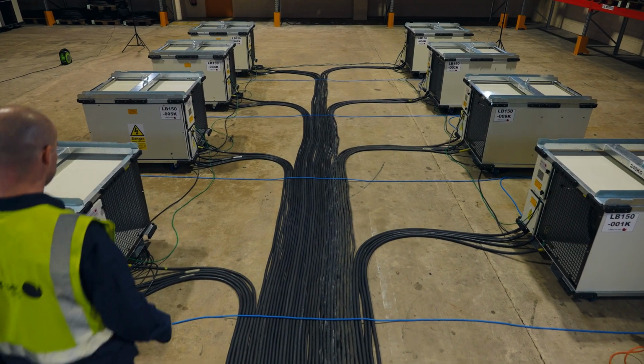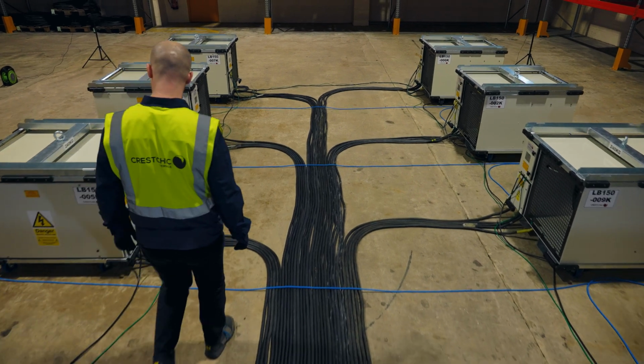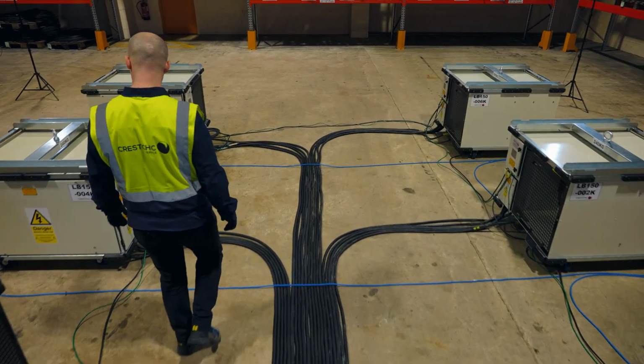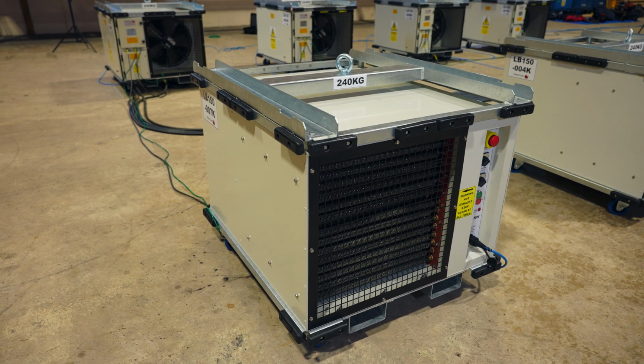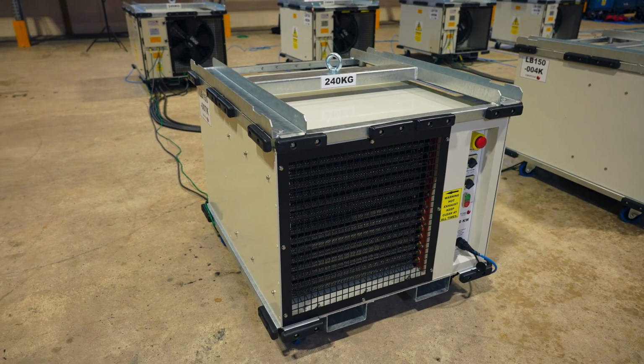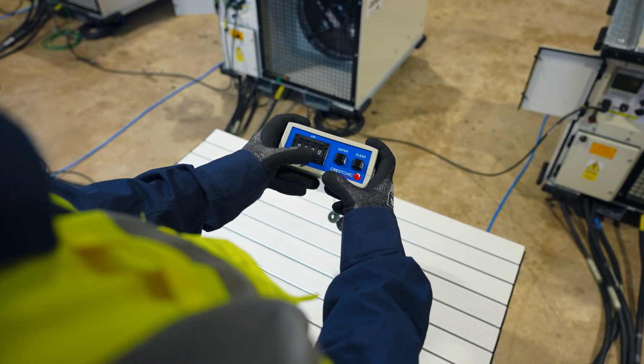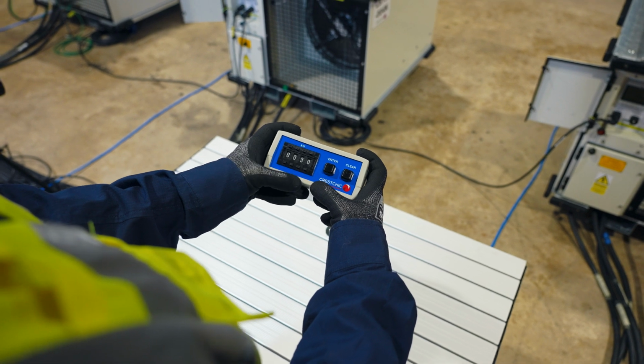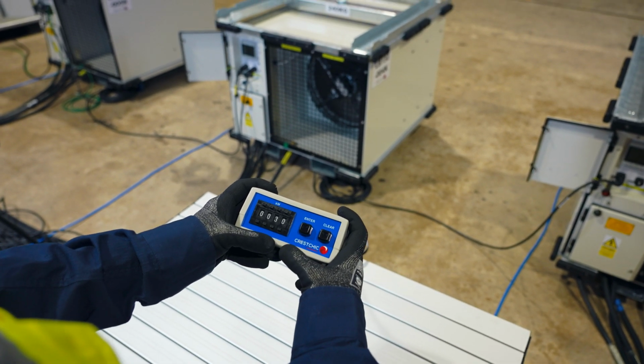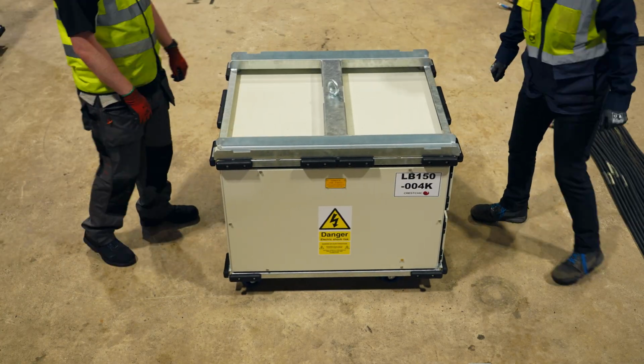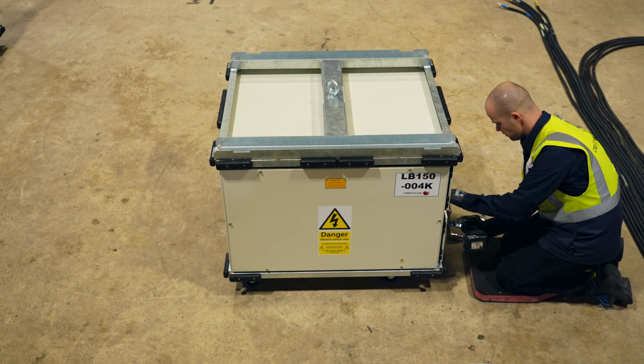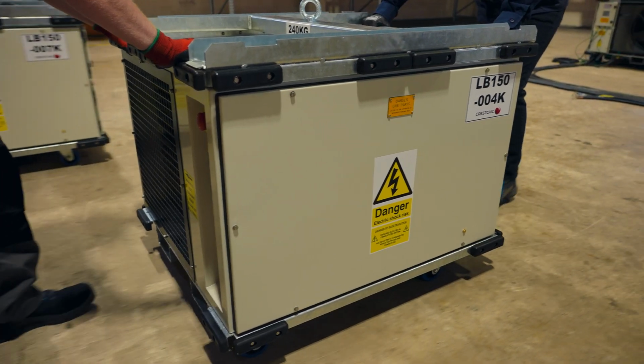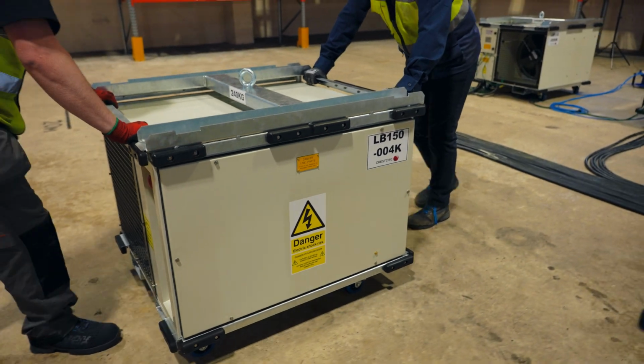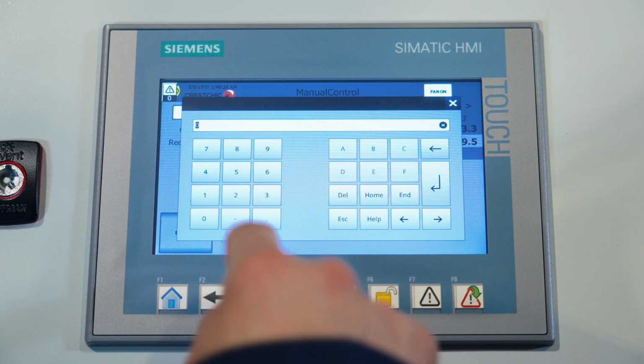We are delighted that you have chosen a Crestchic load bank for your power system testing application. This video aims to show you our load banks being installed and used in data centers to complete load testing and temperature testing, and to mimic the heat generated by rack-mounted servers. This type of load bank has been designed specifically for use in data centers, with consideration made for mobility and size, power rating and a digital controller.